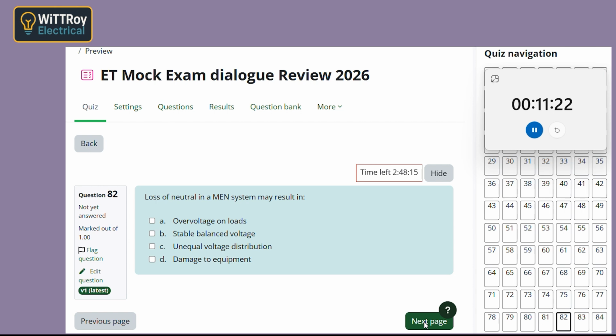Question 82. What may happen if the neutral conductor is lost in a system? I think voltage becomes uneven. Yes, that's a really important one. When the neutral is lost, the balance of the system is affected. So some loads might get too much voltage. Exactly. Some parts can see higher voltage than they should, and others lower. That could damage equipment. Yep, very easily, especially sensitive appliances. So it doesn't stay balanced. Nah, definitely not. That's why that balanced voltage maintained option is wrong.